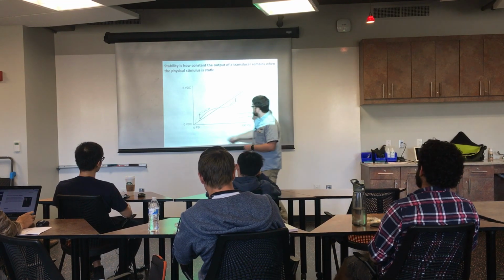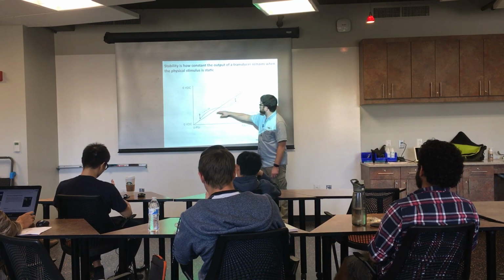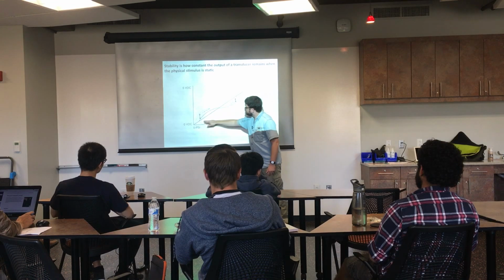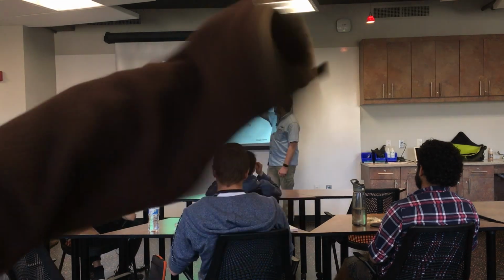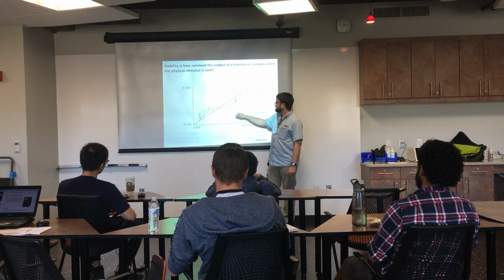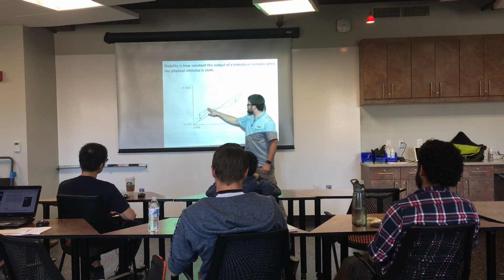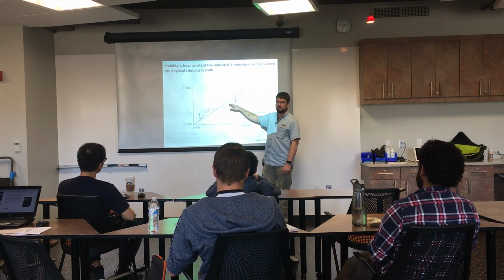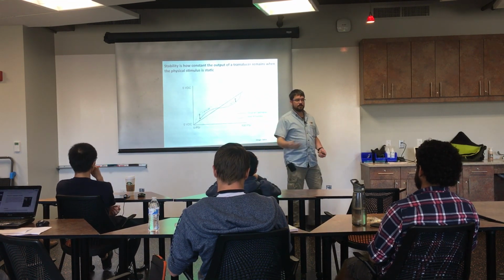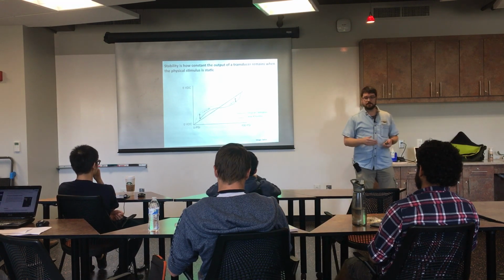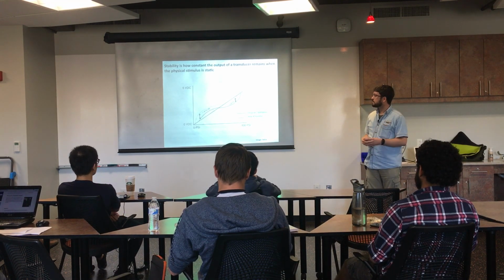So maybe you've got this nice original calibration. This black line would be the ideal. This black curve, let's say this transducer is a little bit nonlinear. And then 6 months later, maybe that calibration curve has moved a little bit. In this case, 0.1% of full scale. But that's something that if you've got a sensor that's out for a very long time, you want to be mindful of.